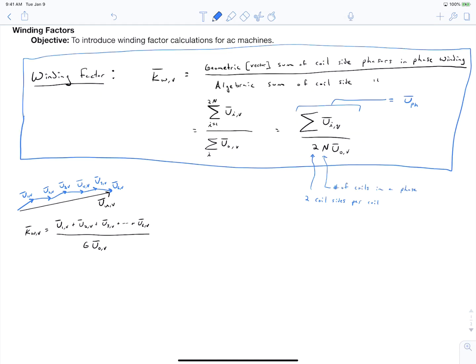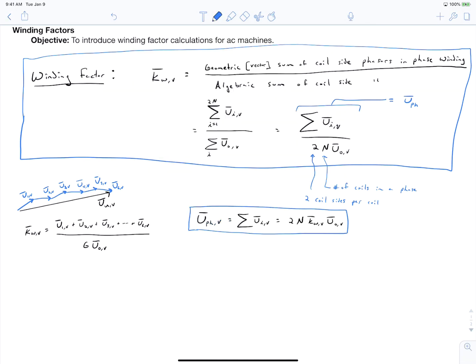From this expression, our phase voltage phasor — whether phase u, v, or w — is the summation of the phasors of all the coil sides. From our definition of winding factor, we can rewrite this as 2n times our winding factor times the phasor of slot zero, i.e., the slot at alpha equals zero. Notice that our winding factor is a complex quantity.